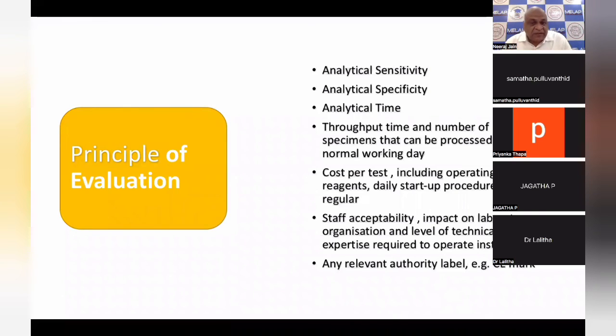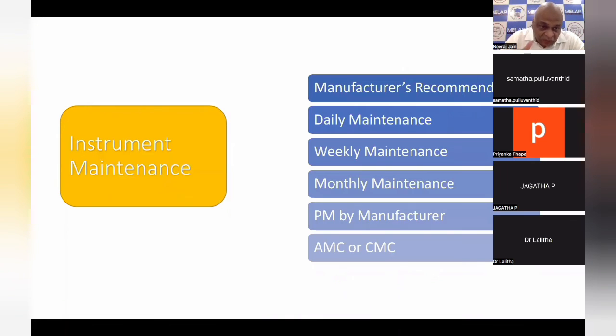Cost per test: not only reagent cost, also cost of the calibrator, cost of the control. A small part of the total cost of the equipment will also go in this. And you have to include all these things, cost of CMC. Then you are calculating cost per test. Staff acceptability: your staff is able to accept all these things and gain all that knowledge. Now, when you're maintaining the instrument, what is required? What are all the manufacturers recommending? What is the daily maintenance required? Weekly maintenance, monthly maintenance, preventive maintenance by the manufacturer. For this, you take an annual maintenance contract or a comprehensive maintenance contract, whatever you are taking. All these things need to be maintained.